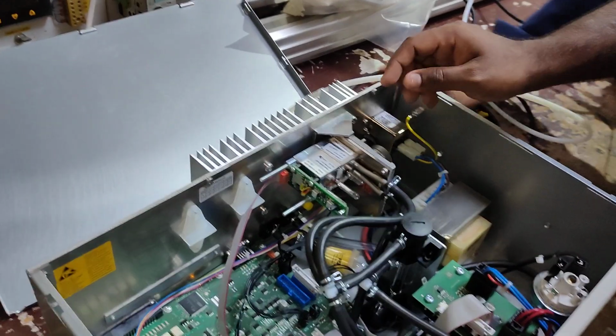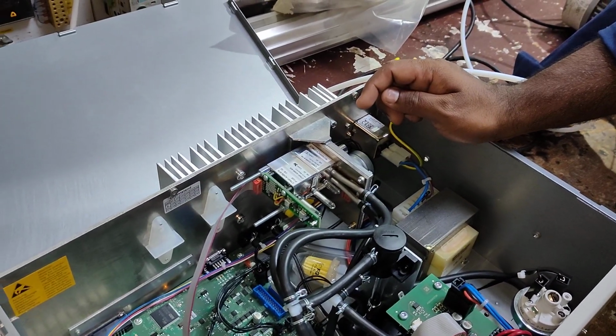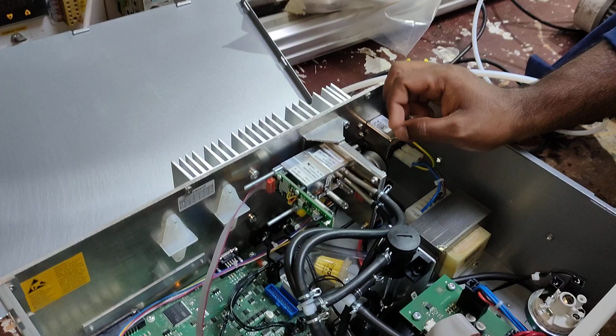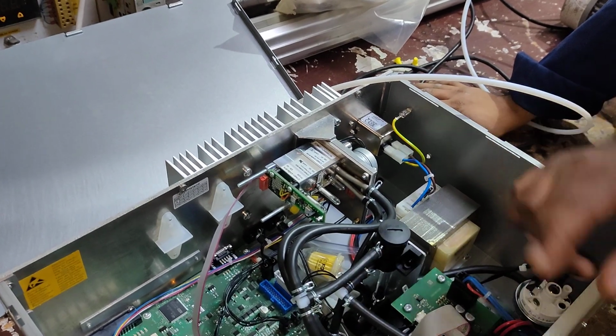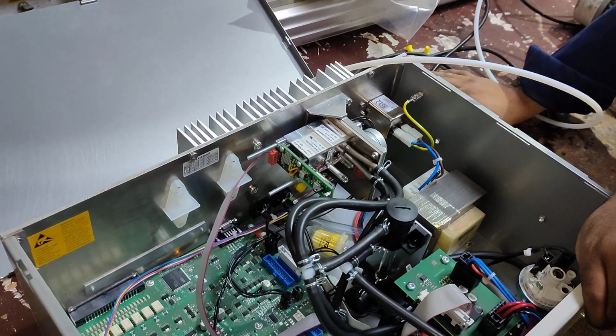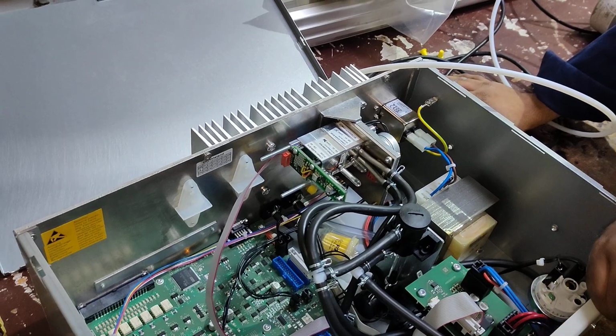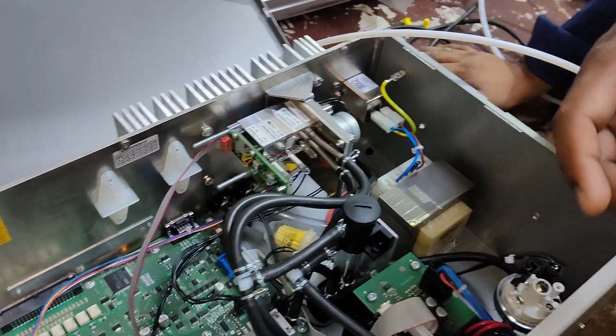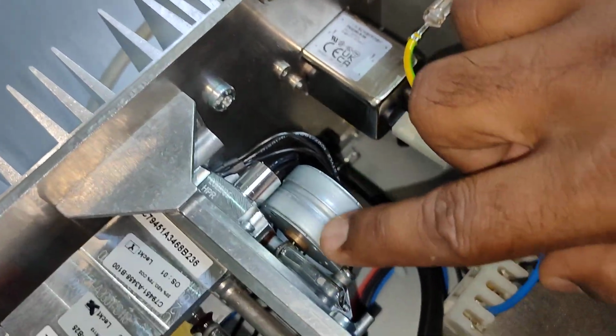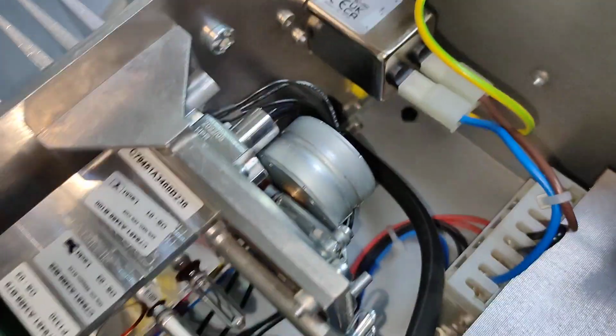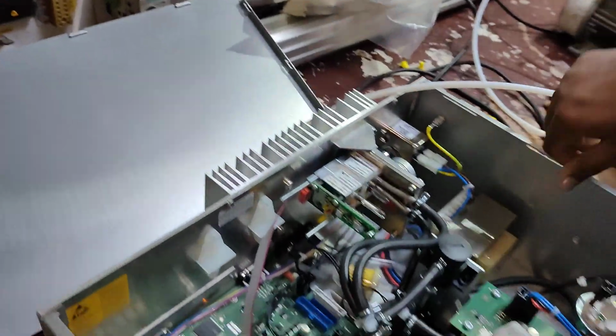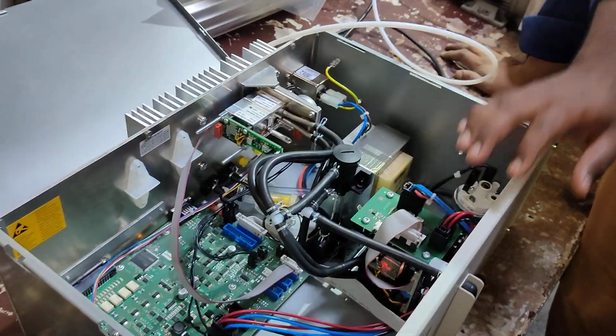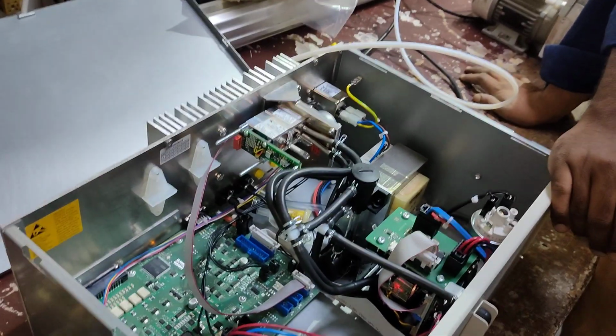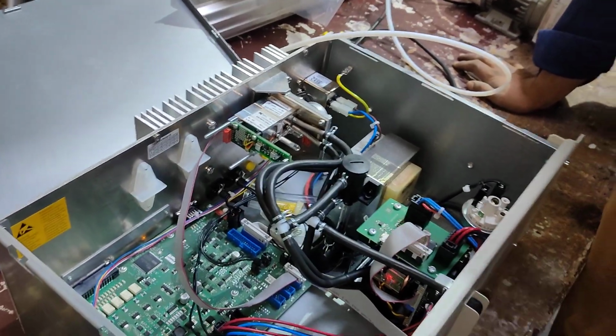Chopper motor, how much voltage will go? Chopper motor is 5 volt DC. We cannot measure that voltage as such in this cable. But if it is working, it's working, or else we have to just replace it. Most of the time it will get stuck if there is a lot of dust. You just have to put some WD-40 on this and it will start running. It is very seldom that the chopper motor will fail for Ultramat 23, unlike Ultramat 6. Only WD-40 is required, not contact cleaner. That is my practical experience.